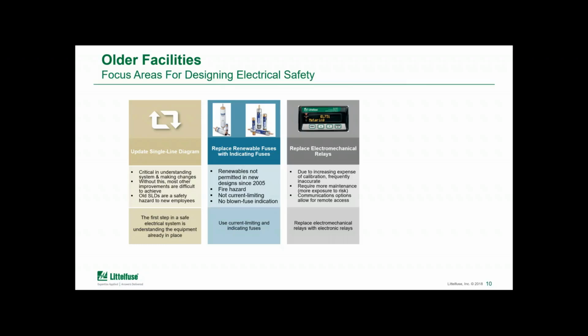But newer microprocessor-based relays, and I guess I'll use newer a little bit loosely because they've certainly been around since the 80s, don't require the same maintenance personnel to enter the cabinet to maintain and calibrate the relays on a regular basis. So that's one benefit. Another, it is getting harder to find people that have the know-how on calibrating the electromechanical devices. In addition, there's more precise measurements and additional protection features as well, and those can certainly improve the safety and even communicate that device through communications to operators or other plant SCADA systems.